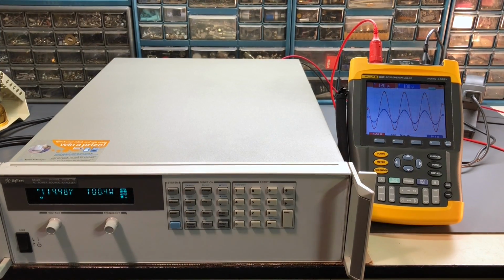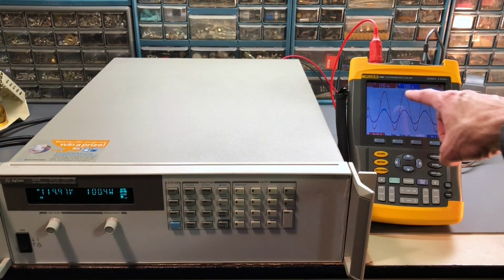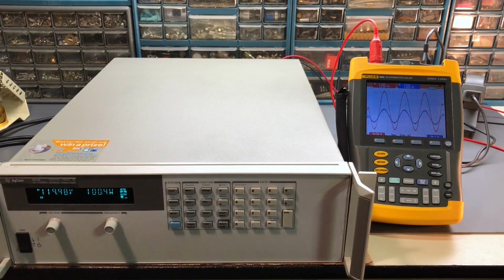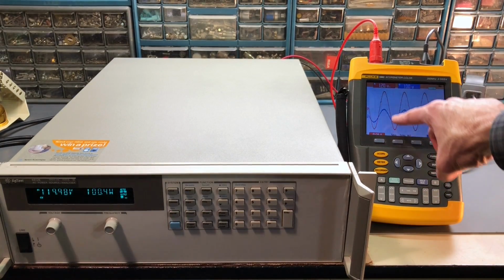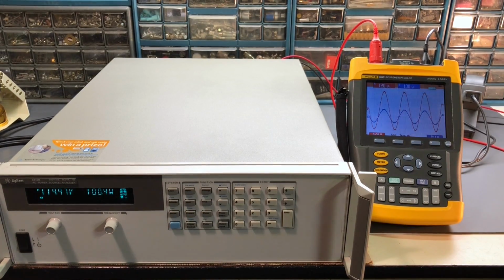Okay, I now have the 6812B connected to a 100-watt incandescent lamp. So that's acting like a load on the power source. You can see the power source is set to 120 volts, and over here we have 119.9897, so no problems there. You can see on the Fluke Scopemeter over here, it's indicating 120 volts. So the sine wave on the output is the red trace. That looks very, very good. No distortion, looks really spot on, no issues with that.